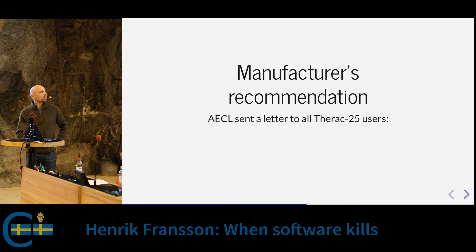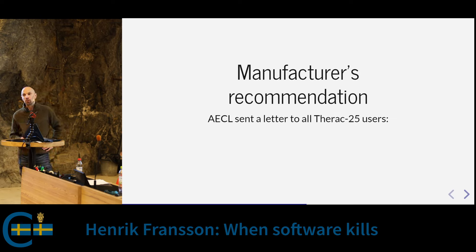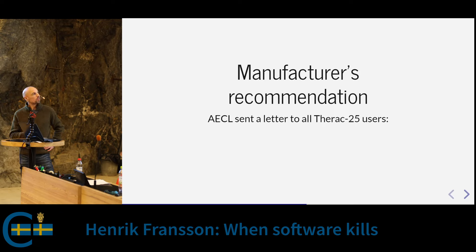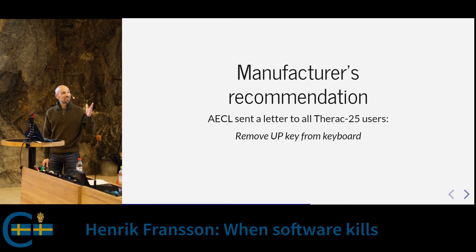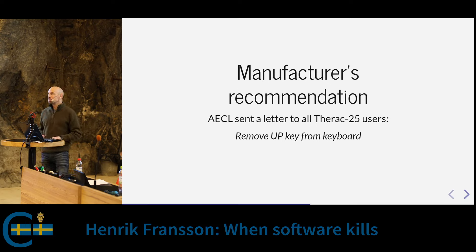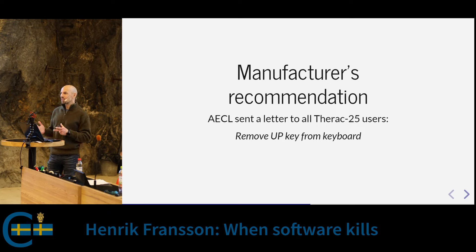The FDA was now on to them, so the manufacturer sent a letter to all users. Since changing modes involved pressing the arrow keys to confirm, their fix was: remove the up arrow key from the keyboard — mechanically remove it so you physically can't go back and change values. The authorities were not very happy with this response.